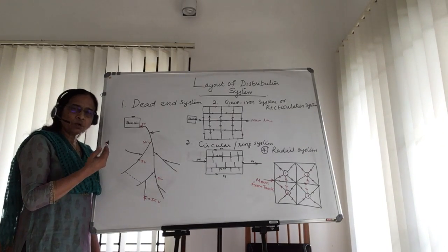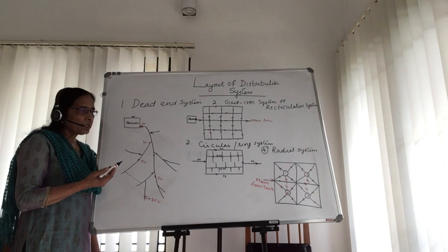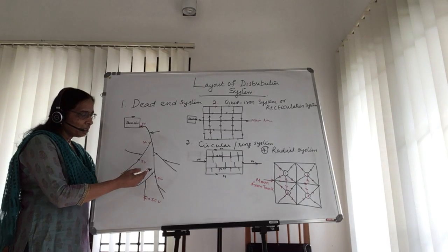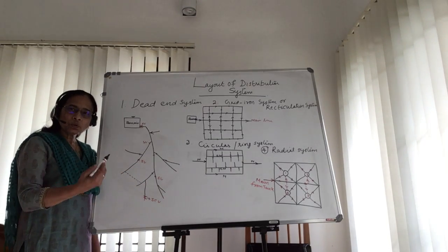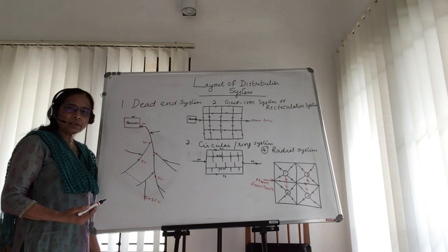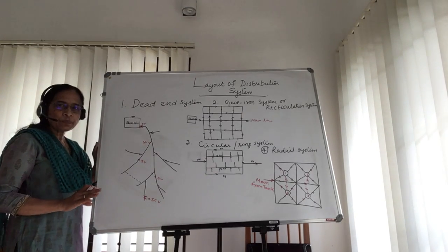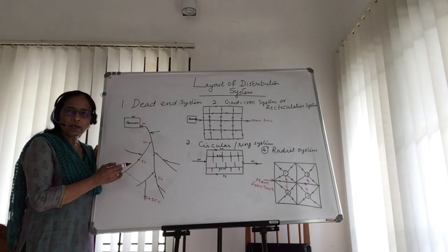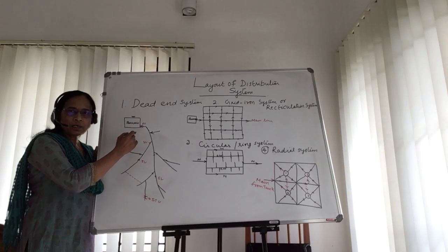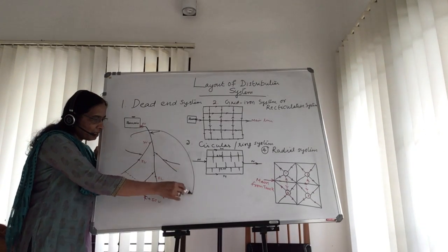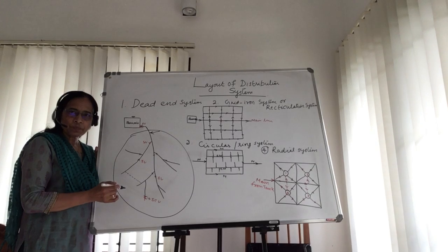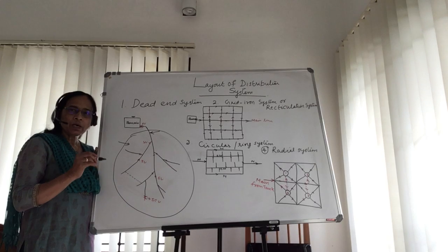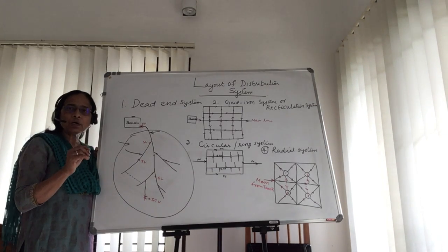And if this reservoir is located in the farthest end of the city, because of our location or because of the treatment plant site or because of the gradient which we require, then again you have to plan whether this line has to pass through the city or through the other by lanes, and whatever be the options, our objective is to lay the pipeline so that the entire area can be supplied water to a required pressure or to a minimum required pressure, and the quantity you have to give equitably.